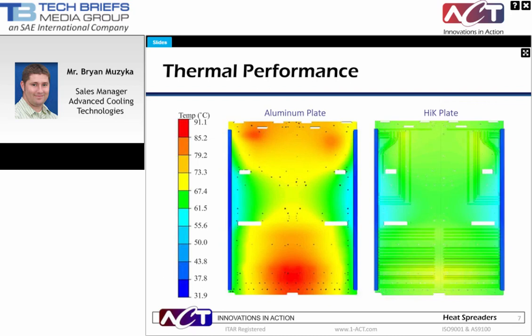This figure shows a comparison of aluminum plates with a high-K plate. In this example, the system was cooled using liquid-cooled rails. With straight aluminum, shown on the left, conduction gradients created hot spot temperatures exceeding maximum electronics temperatures. Going to a copper solution was not desirable due to weight concerns. So we embedded heat pipes, and using a high-K solution, we got higher performance than aluminum or copper without adding significant weight. For this program, we achieved over 20 degrees C hot spot temperature reduction.